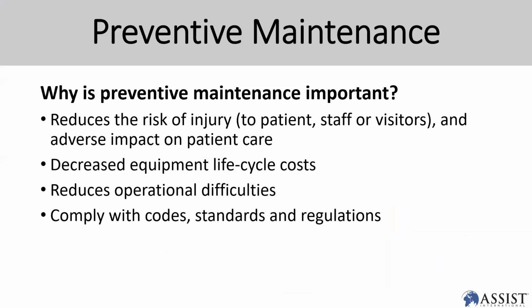Okay, patient monitor preventive maintenance. This is one of the main important topics. So as usual, why is preventive maintenance important? To reduce risk of injury to the patient, staff, visitor, and even the BMET itself. These are very important parts of it. To increase the life cycle of the patient monitor and decrease the maintenance cost of the particular equipment. So reduce the operational difficulty. What happens is, if your NIBP curve is not good, you have difficulty using it. By doing preventive maintenance and all this checking, you know exactly when something needs to be replaced. So the operation of the particular unit can be constant and easier.